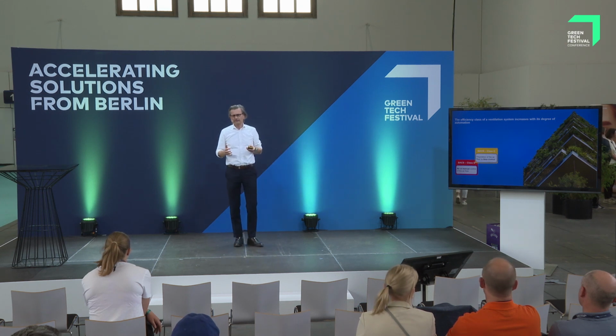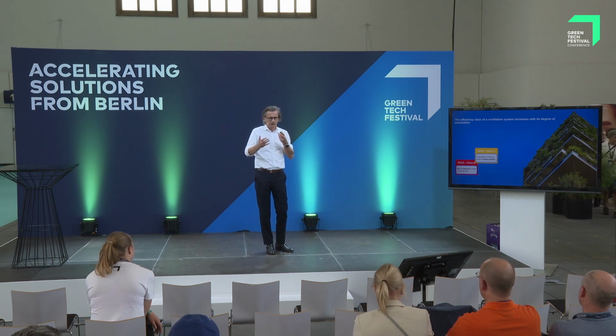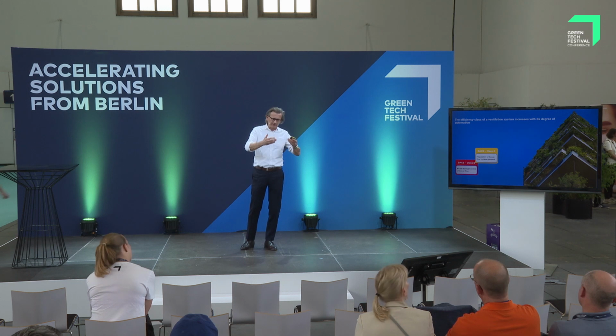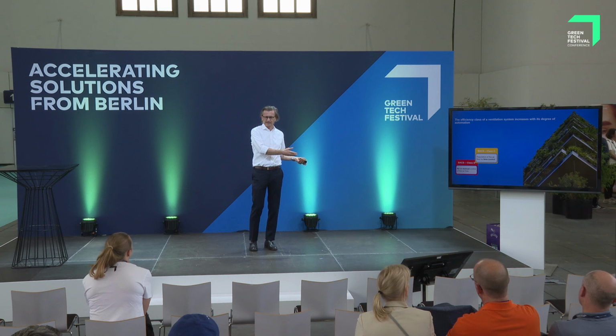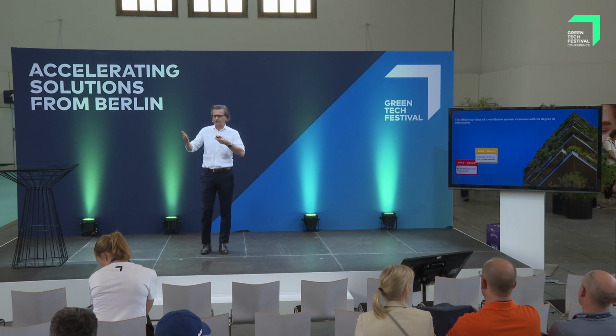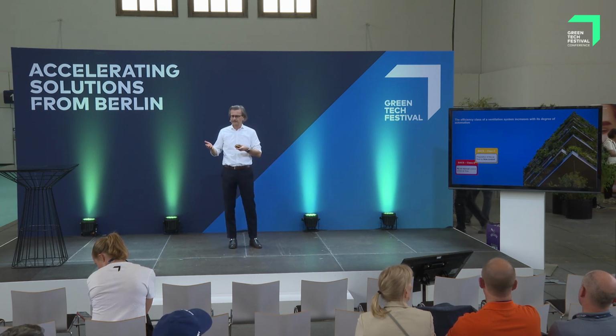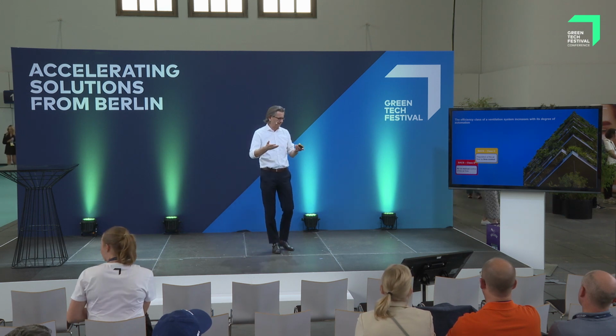The second class, building Class C, is a class that goes with office hours. But if there's nobody who's really taking these office hours into the system, then you automatically have a system D. So if there is no facility manager taking care of the office hours, taking care of Sundays and Saturdays and opening in the evening and all these things, then you automatically have a Class D building, which is always on.